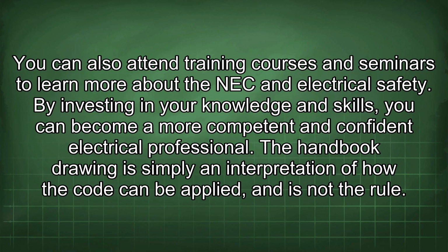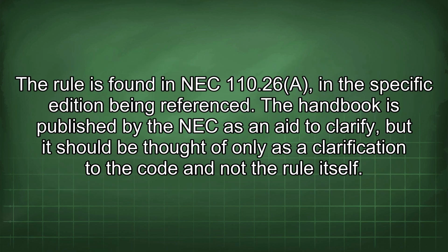The handbook drawing is simply an interpretation of how the code can be applied, and is not the rule. The rule is found in NEC 110.26(A), in the specific edition being referenced. The handbook is published by the NEC as an aid to clarify, but it should be thought of only as a clarification to the code and not the rule itself.